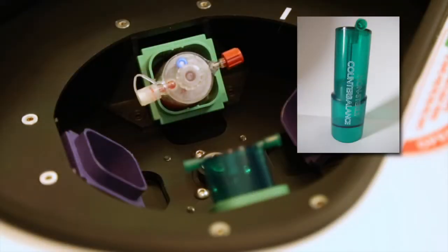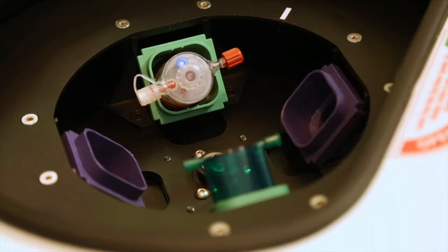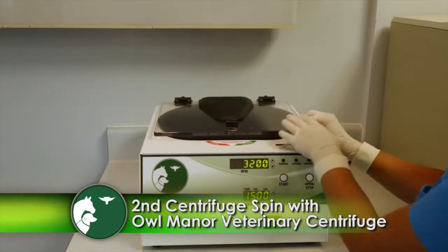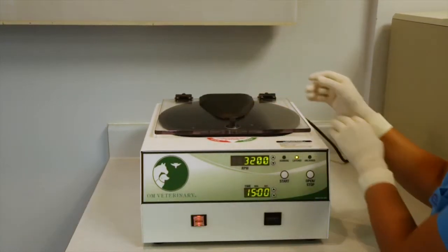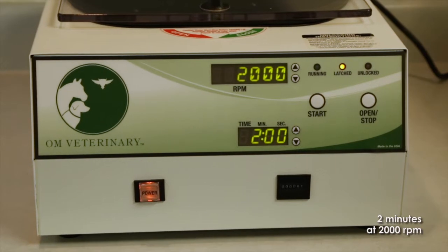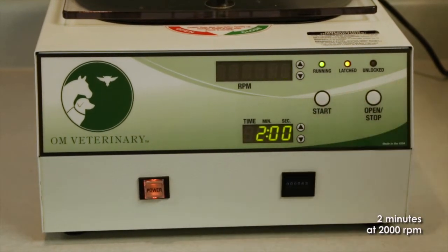The Pro-Stride counterbalance is weighted to appropriately balance the concentrator device. You will need to remove the counterbalance used in the first spin. Again, make sure to load the device with the ports placed horizontal, facing left and right, and not vertical. Alternatively, if a second Pro-Stride kit is being used, this will serve as the appropriate balance. And again, the green centrifuge buckets must be used with Pro-Stride. As done before, close the lid and secure the latch on top of the centrifuge. Set the RPMs to 2,000 and time to 2 minutes and push the start button.